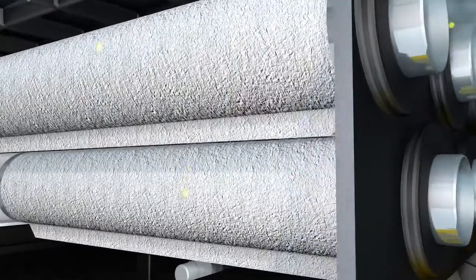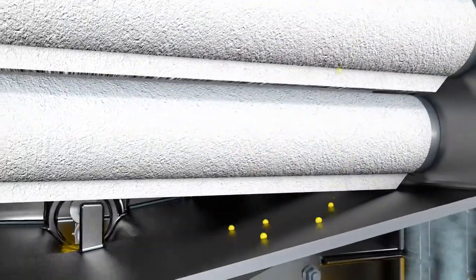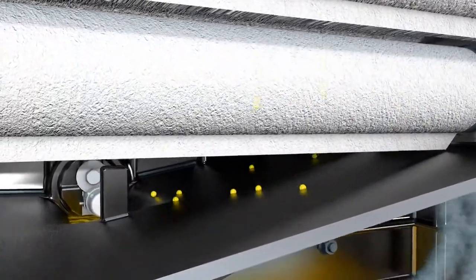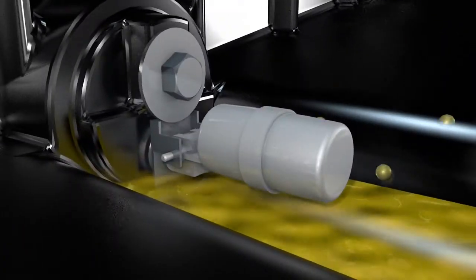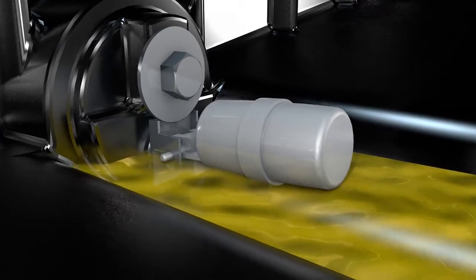Due to the low gas speeds, almost exclusively oil aerosol enters the exhaust filters. Eventually, it leaves the exhaust of the pump. The aerosols condense in oil droplets in the exhaust filter. This recovered oil is collected and sent back to the pump once the float valve opens.